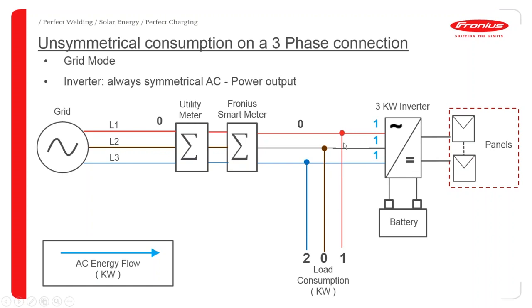So in this situation, we'll do a bit of analysis. You can see here, just because it's a white piece of paper, I've got blue, black and red instead of the white phase. But let's use it as phase 1, 2 and 3. So you've got phase 1 here, the red phase. Let's say that's got 1 kilowatt worth of load. The black phase here has got 0 and the blue phase has got 2. So in this situation, the inverter is producing 1 kilowatt.